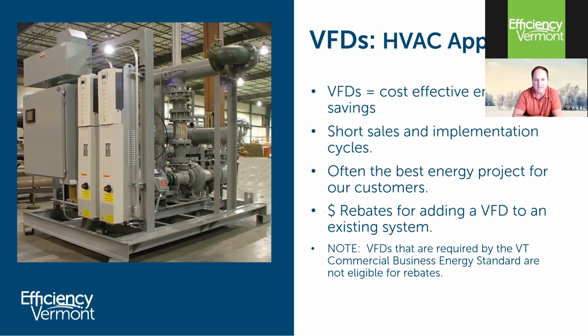This market has been hit by the supply chain issues, just like everything else. There's plenty of electronics and chips in these boxes, so we've experienced some delays in the supply chain. But there is still product out there. We check with our supply chain partners all the time. Last check, there were over 50 OEMs of VFDs, so there's certainly still supply. Most of the drives that we see in Vermont are probably 30 horse and lower, with the average drive on an HVAC application being in the 10 horsepower range.